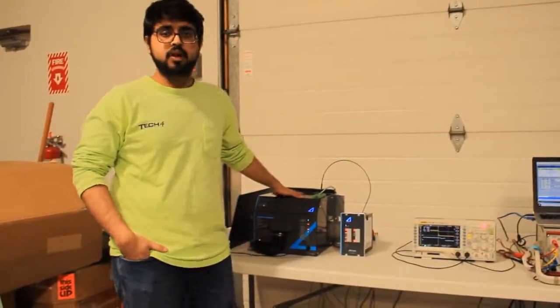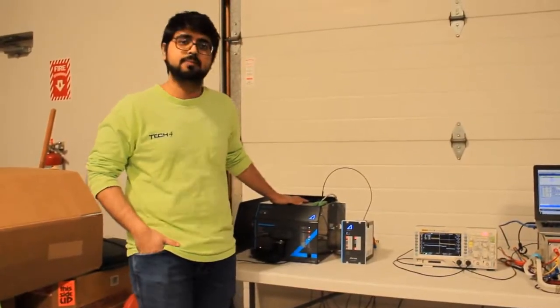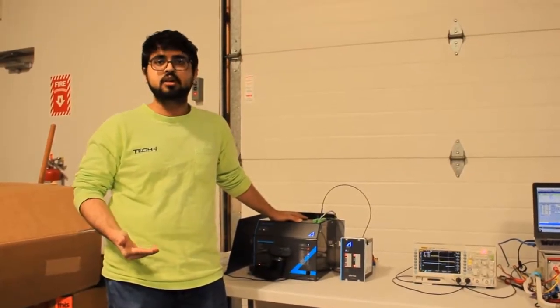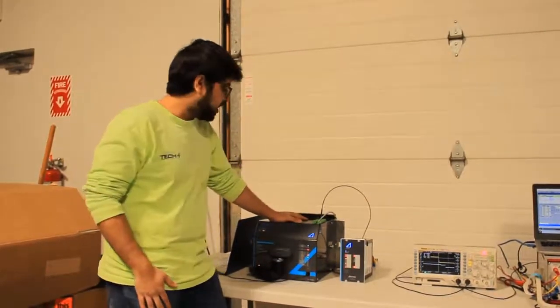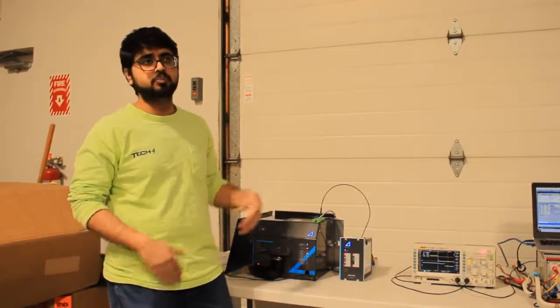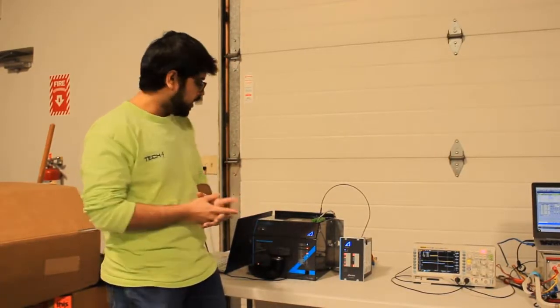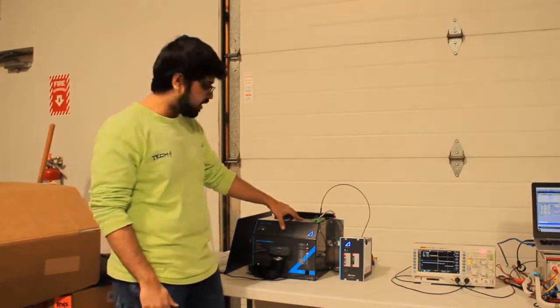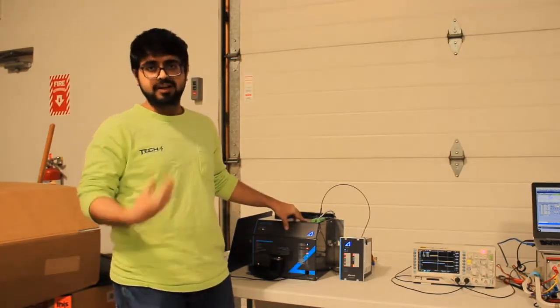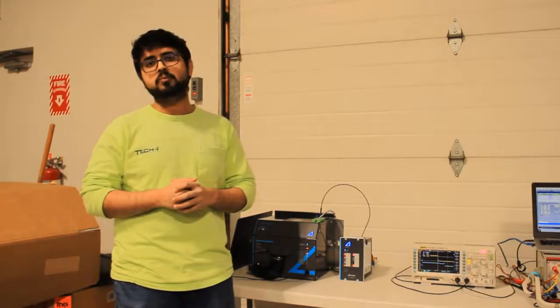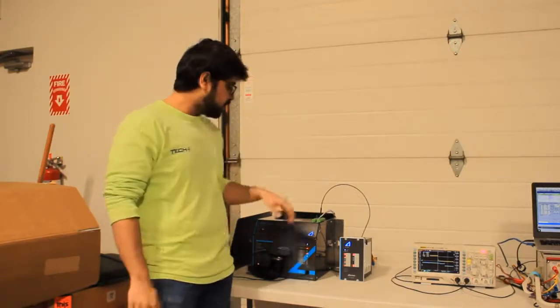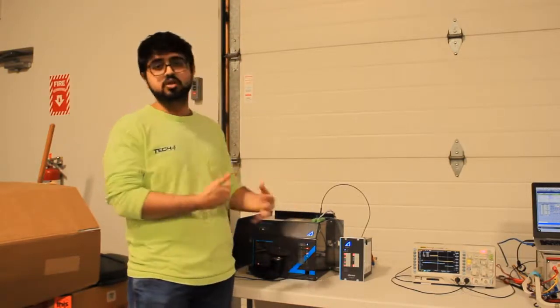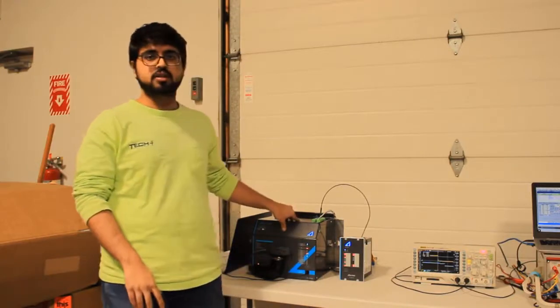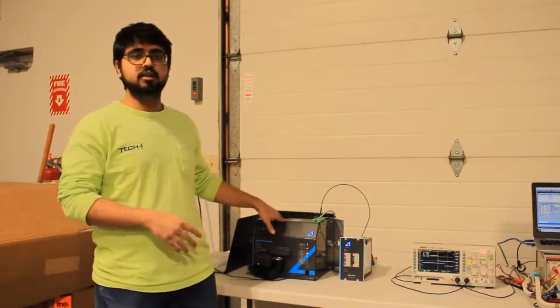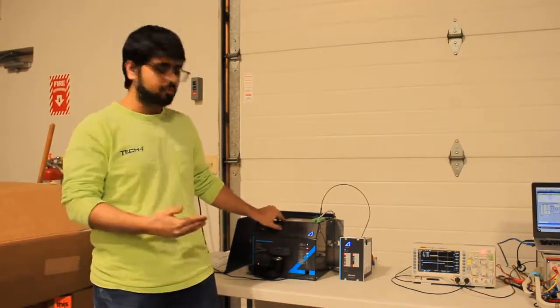One other thing about the ArcTech AQ1000 device is it's the only resettable arc quencher device in the market, and an arc quencher AQ1000 trips up to 4 times under load. But there is no way of knowing. There's no way the AQ1000 detects that you're testing it. So ArcTech has built in a commissioning mode, which helps us, which is used while testing. So the AQ1000 knows it's not under load and it's not in use, so it bypasses the trip count.